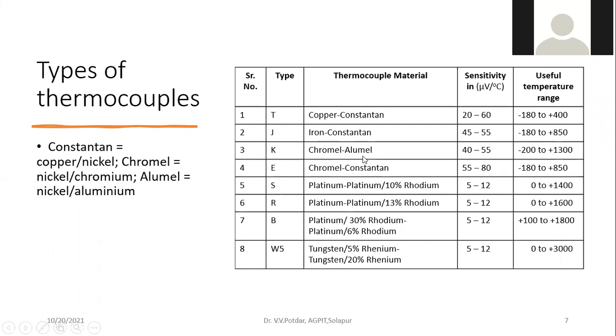K-type is chromel alumel type. The sensitivity varies between 40 to 55, and the temperature range is minus 200 to plus 1300. So K-type provides me a bit broader temperature range, isn't it? So depending on the temperature ranges I want in my industrial application, I should select appropriate thermocouple, either T-type, J-type, K-type, E-type, S-type, and so on and so forth.